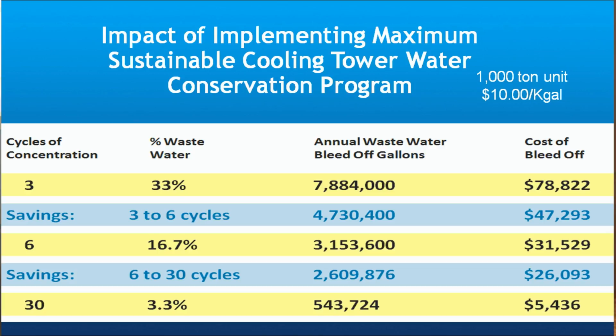There are hundreds of thousands of cooling towers that range from 2,000 to 10,000 to 20,000 tons and higher. They could most definitely benefit from raising cycles of concentration beyond 3 or even 6 cycles of concentration. This is sometimes not possible with traditional chemical scale inhibitors because of the need to bleed excessive amounts of water in order to maintain complete system integrity. But remember, there can be no conservation if it's at the detriment of the cooling tower system, equipment, and the operation, which, as we all know, can be very expensive.